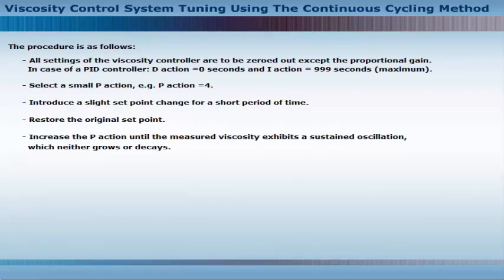The procedure is as follows: All settings of the viscosity controller are to be zeroed out, except the proportional gain. In case of a PID controller, D-action equals 0 seconds and I-action equals 999 seconds. Select a small P-action, such as P-action equal to 4.